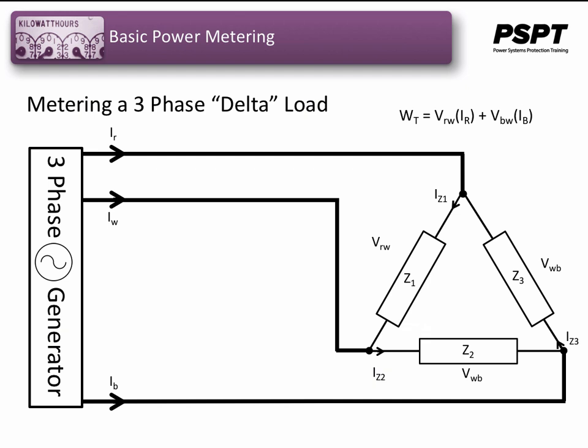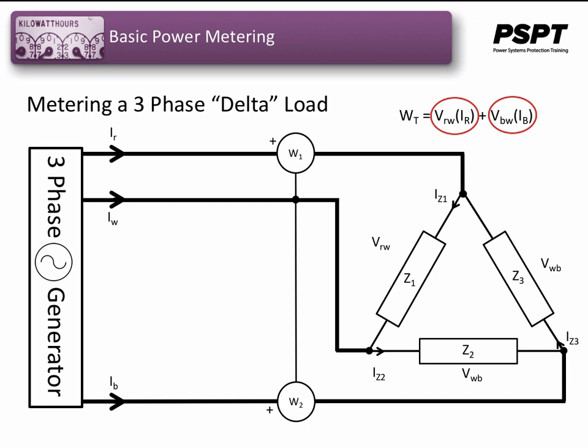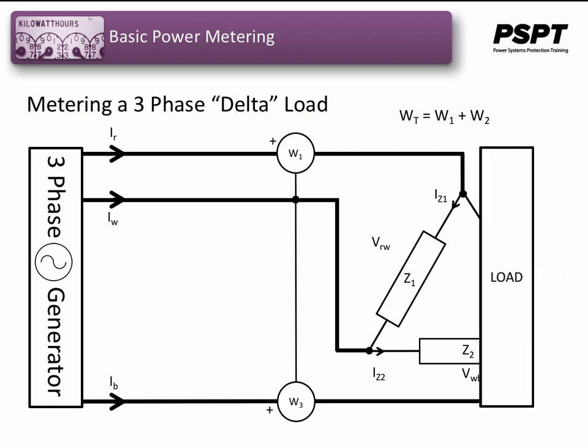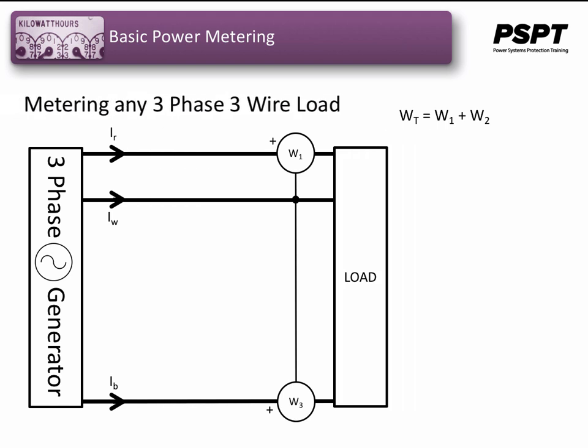This formula tells us that we only need 2 meters, or one 2-element meter, to measure the power consumption in a 3-phase 3-wire load. One meter element uses the red to white phase-to-phase voltage with the red phase current. The other meter or element uses the blue to white phase-to-phase voltage with the blue phase current. Since the measurement of power to the load only uses phase-to-phase voltages and phase currents, the load configuration doesn't matter as long as there are only 3 wires to the load, that is, no neutral.